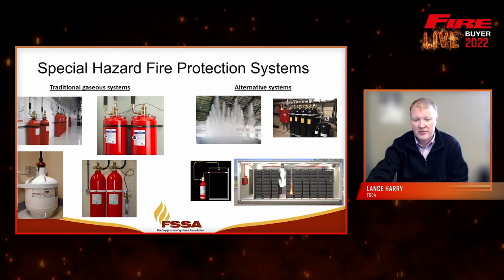In the bottom left, you see another kind of hybrid system. This uses a storage container of traditional gaseous agent, but the detection system is a bit different. The red depicts pressurized tubing that can burst and allow the system to discharge through the yellow tubing into the protected space.